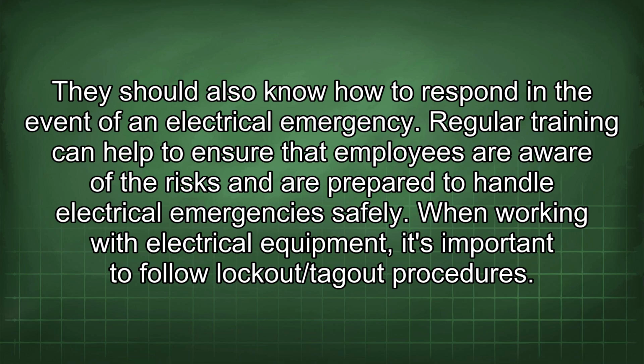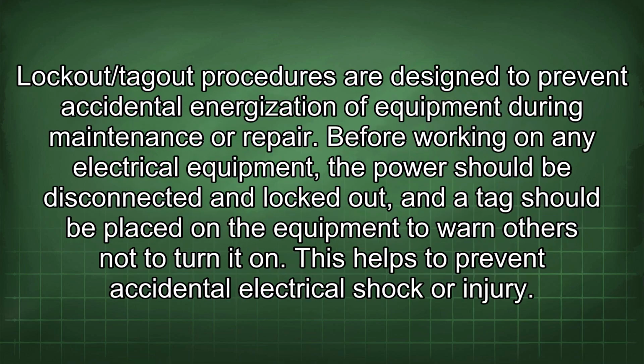When working with electrical equipment, it's important to follow lockout/tagout procedures. Lockout/tagout procedures are designed to prevent accidental energization of equipment during maintenance or repair. Before working on any electrical equipment, the power should be disconnected and locked out, and a tag should be placed on the equipment to warn others not to turn it on. This helps to prevent accidental electrical shock or injury.